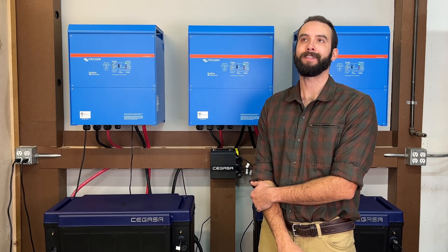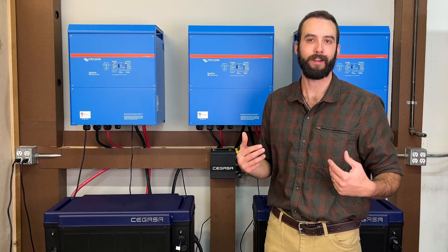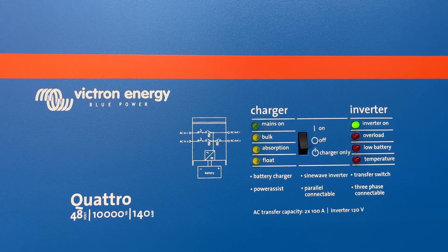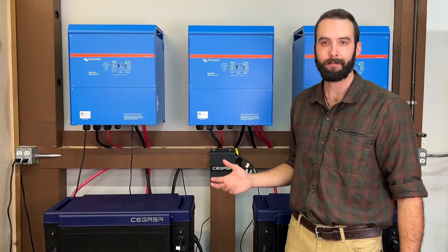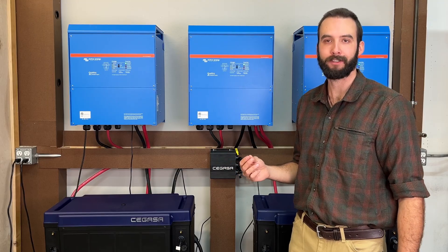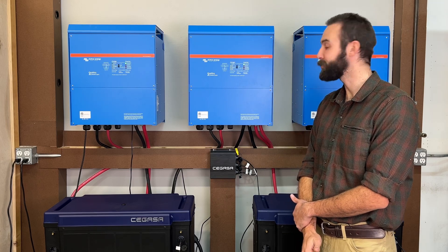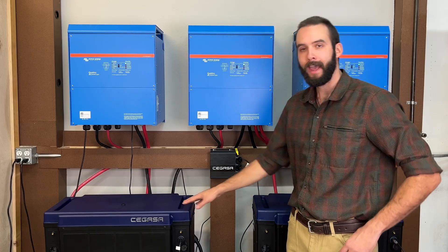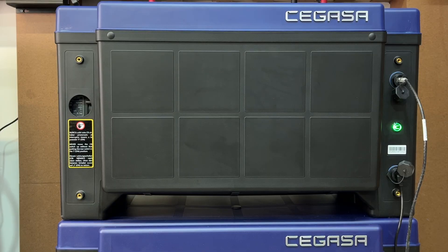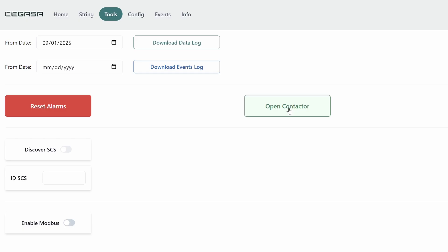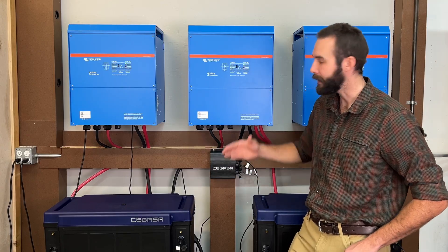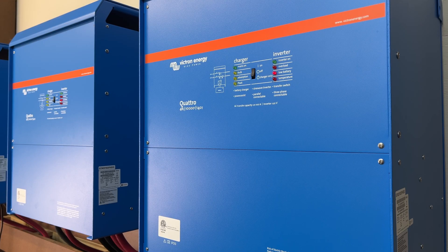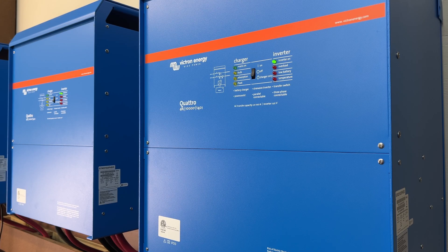Now let's talk about, as a guy that sometimes goes into the field, personally, my favorite element. Up here on the wall, I've got three Quattro 10Ks. It's 30 kVA of inverter from Victron. And if you've ever put one of these bad boys up on a wall and tried to power it up, you'll know that it has a very, very, very hungry capacitor inside of it. Oftentimes, most batteries struggle to provide that in a single soft start cycle. The Cegasa have an actual resistive circuit inside of them. They've got a soft start feature. You'll actually see as they go into it and you activate that soft start function altogether, they will slowly ramp up that voltage. We'll see the Quattro hit a low battery, then full voltage, and then come up and turn on. I've actually been able to turn on all three of these Quattro 10Ks with a single unit of Cegasa.